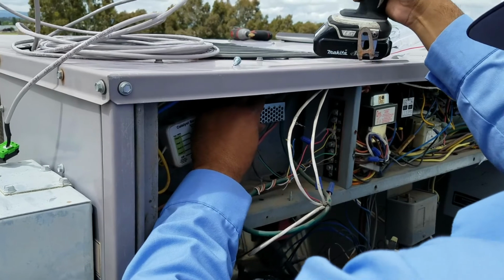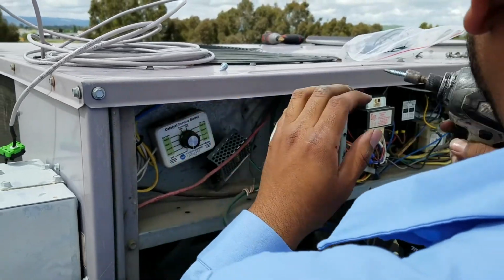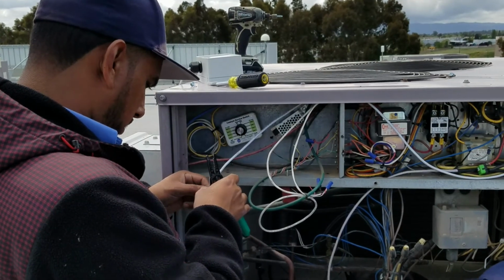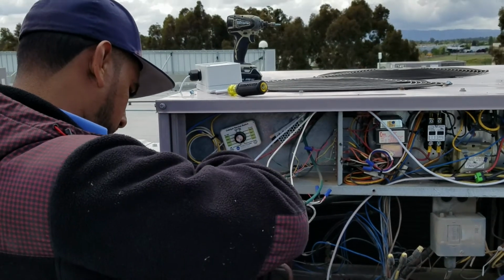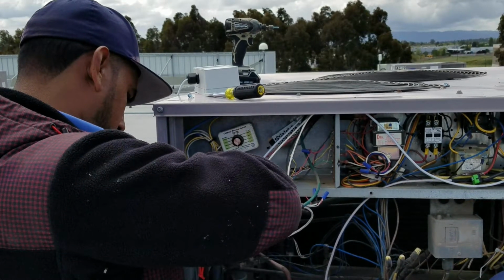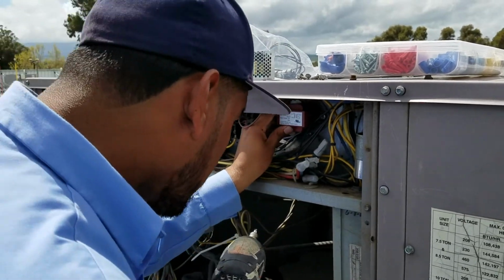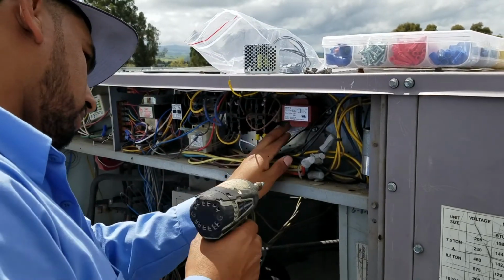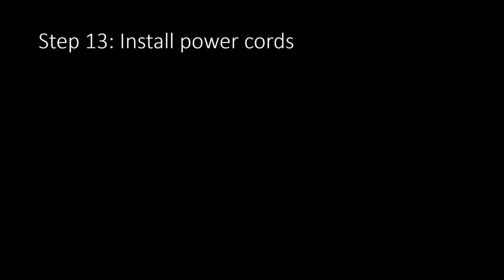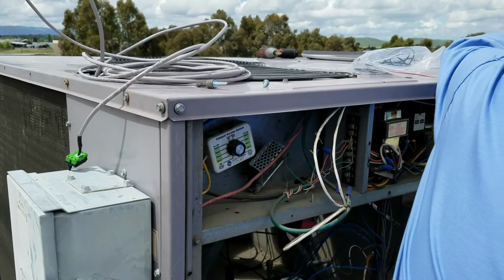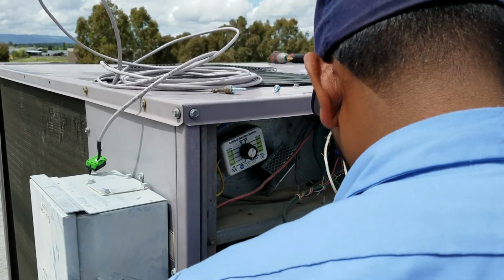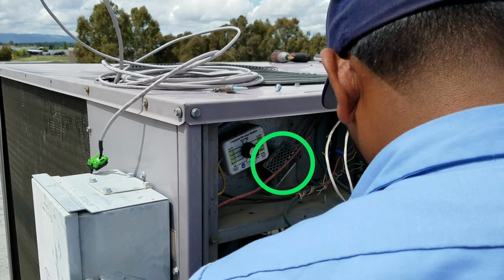Step 12. Power supply. Place the power supply in the service panel at the location you marked in Step 2. Connect the power supply to the 110 volt to 240 volt alternating current power supply. If the HVAC unit has 460 to 480 volt power, then use the step-down transformer. Step 13. Install power cords. Run power cords from both the modem and DCU to the power supply. Install wires onto the power supply.